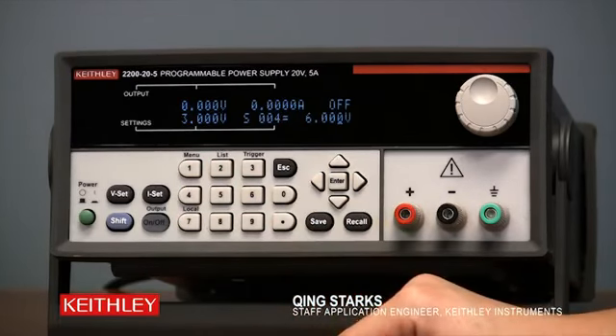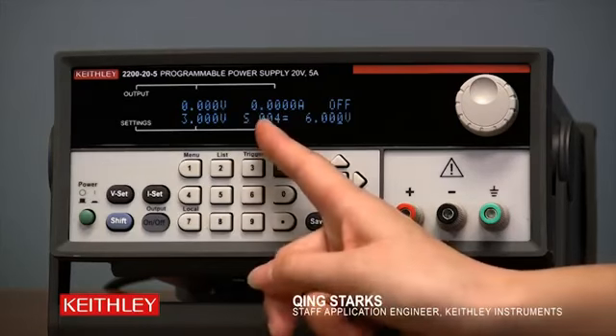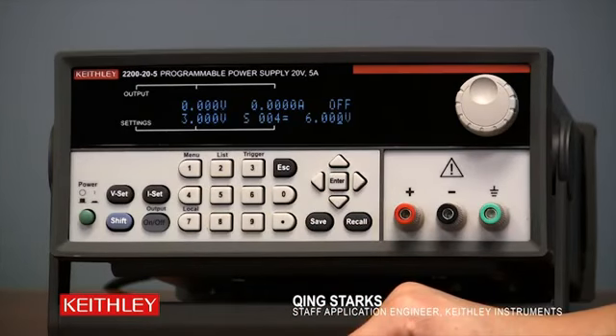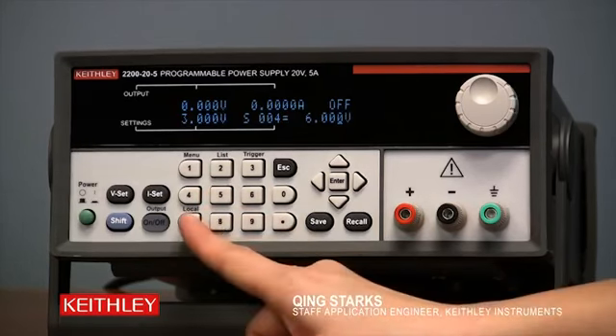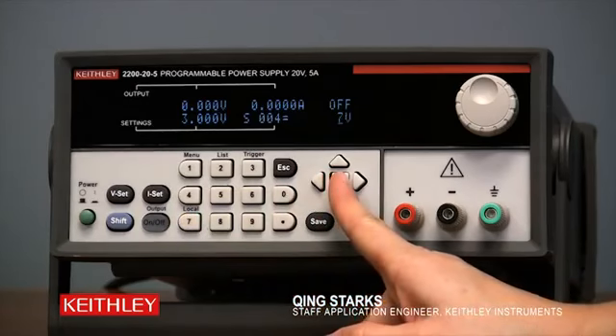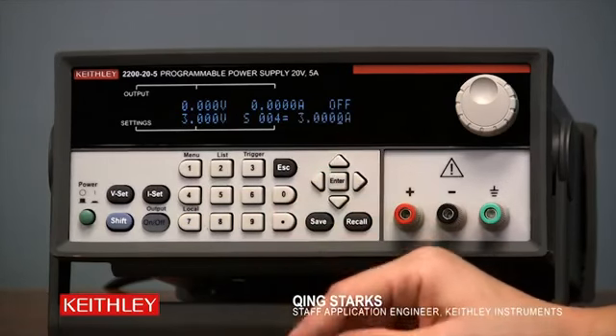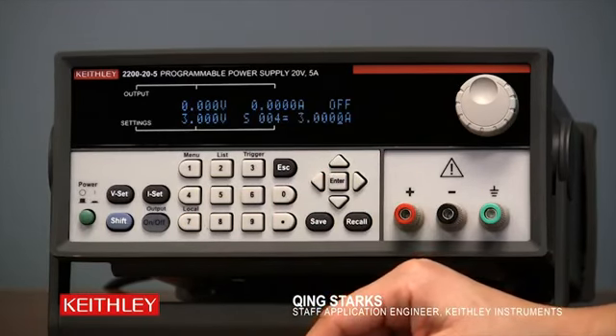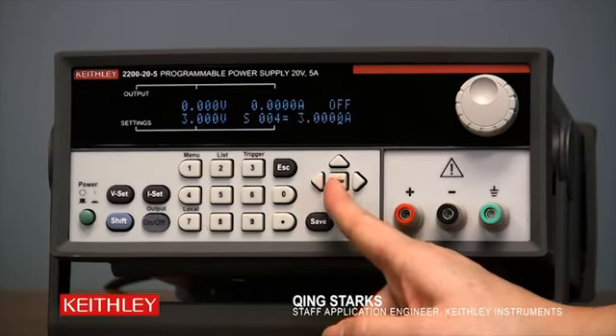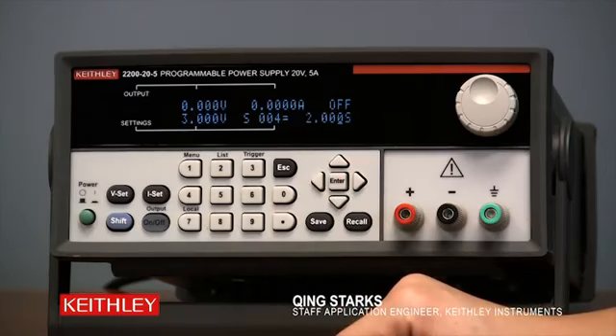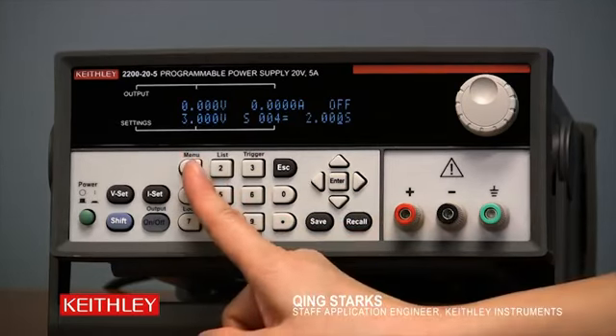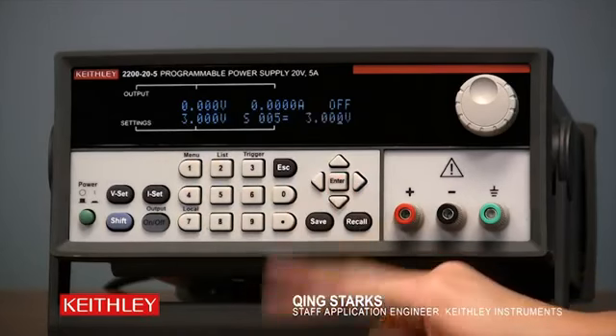Step 4 is currently set to 6 volt. As you can tell, the display is showing S004 equals 6 volt. And we can change that to 7 volt by pressing 7 and then Enter. And then we're setting the current limit for this step. Currently, it's set to 3 amps, and we're happy with that. We can just press Enter. And the duration is set to 2 seconds. We can change that to 1 second and press Enter.